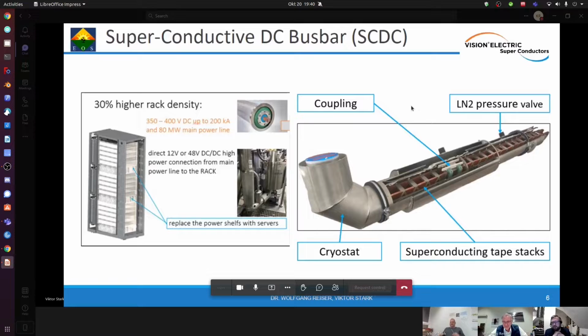As you can see, that's a module. You can realize bending radii as you need them. It is a double-walled steel cryostat with vacuum between the two walls for isolation reasons. In there you have the superconductor tapes or the stacks. What you can also see is a pressure valve here. You have to move the liquid nitrogen, which is inside the system, and with this valve, for example, you can regulate the overpressure if this should occur, which is normally not given, but it's just a security feature.